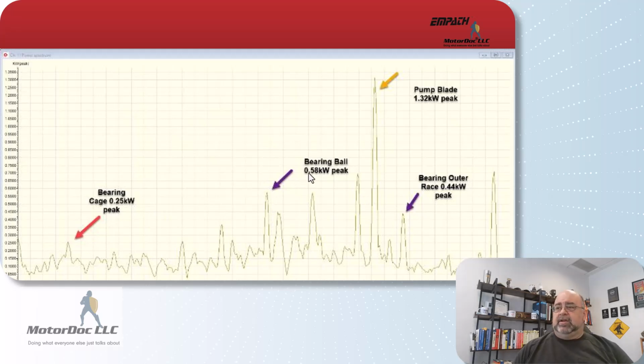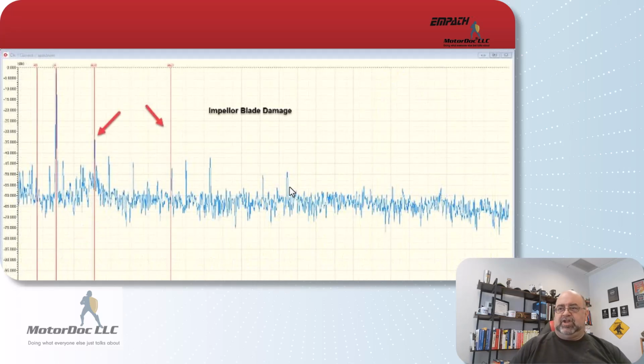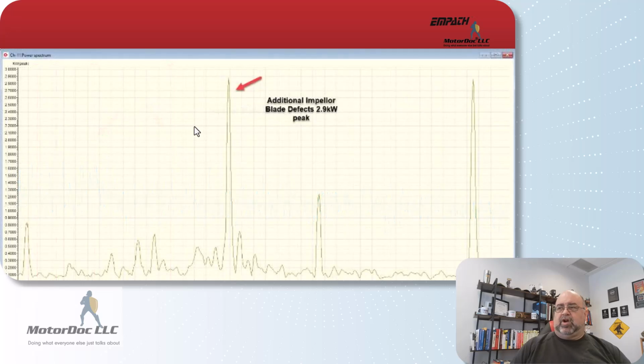So the bearing, the cage, the ball and the outer race, these each will add up. Now 6322 is a gigantic bearing. And then the pump blade, which turned out to be a nick in the blade, caused a bit of trouble here. So up to 1.3 kilowatts in your larger machine. But you notice that this is well under the 10 kilowatts losses in the machine. There is some additional impeller blade problems, which we see here, which is almost 3 kilowatts. That's driven equipment related stuff.